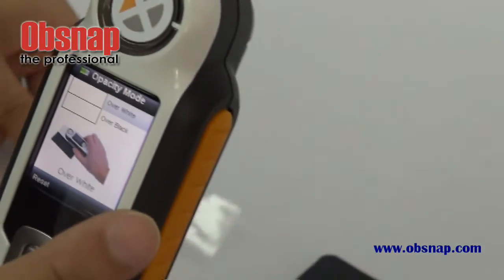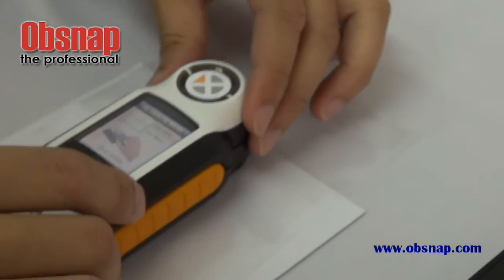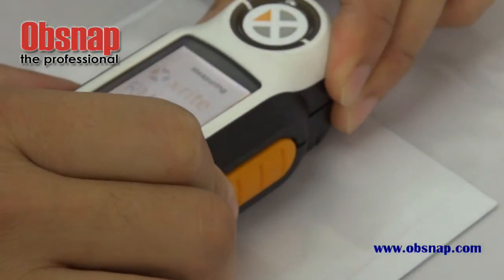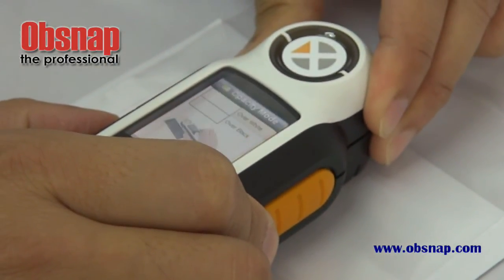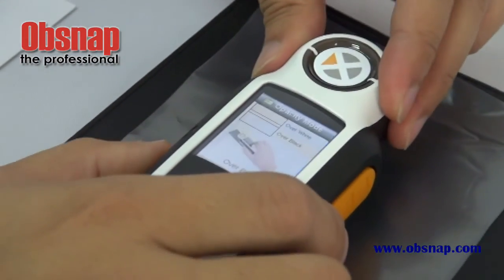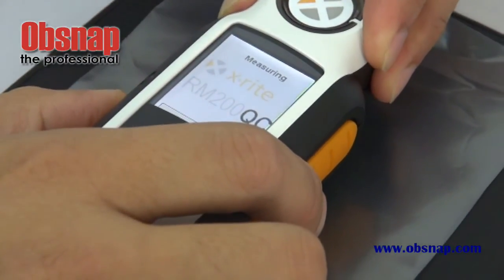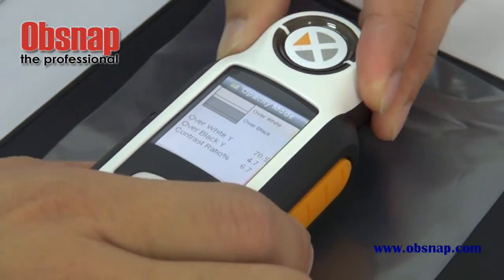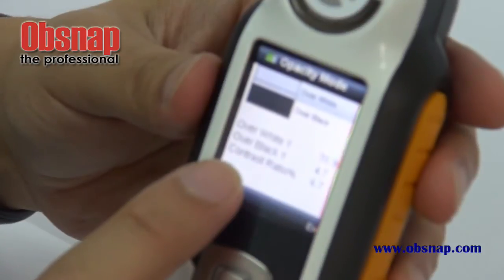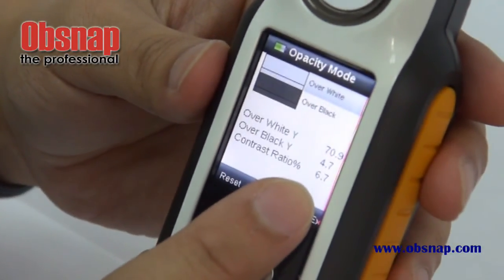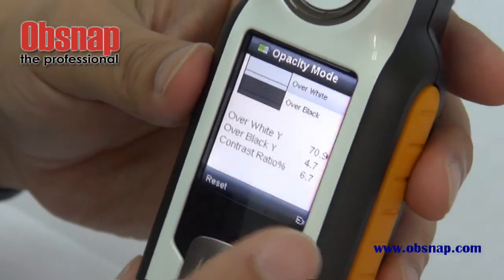The sample is put on top of the white background and we measure. Then it will ask us to measure over black, the sample is put on top of the black background, and we measure. So it will tell us the contrast ratio is 6.7. It's very low opacity because this is actually a very high transparency product.